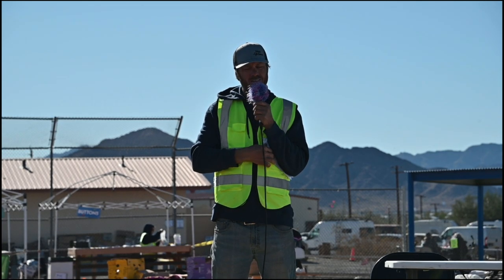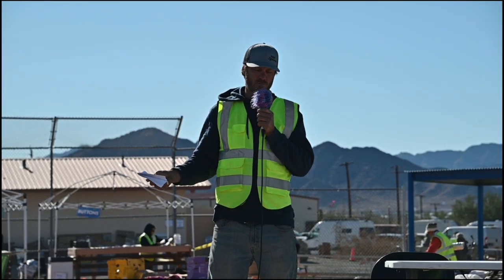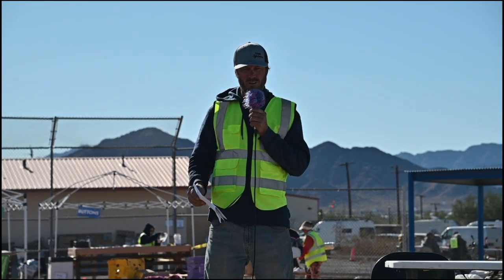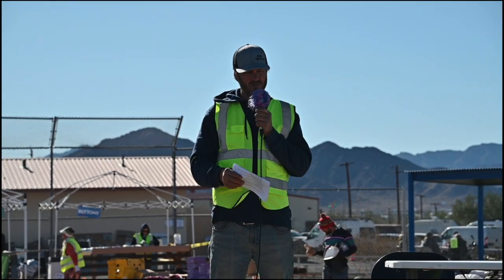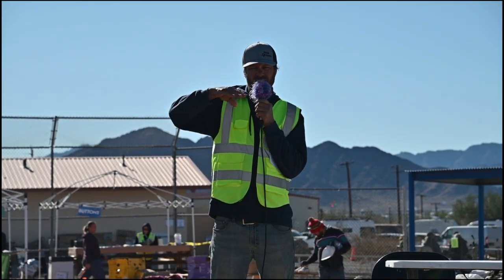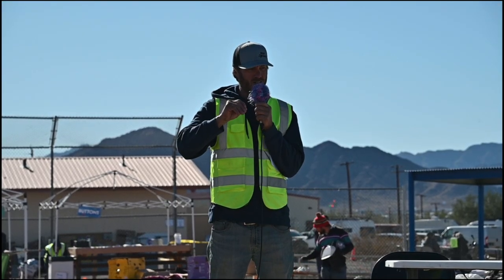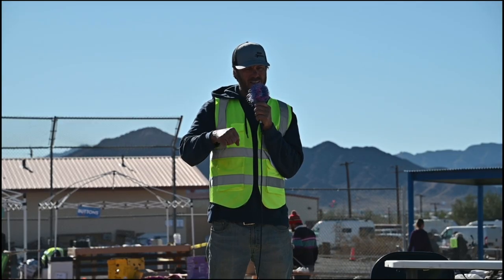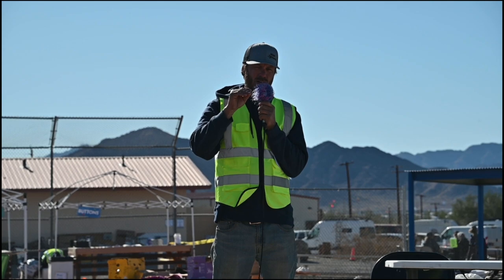So a loose connection on a fuse, if you're trying to pull low power, if you're trying to pull 5 amps, 10 amps, it'll probably go through no worries. But if you've got a 150 amp fuse and you're trying to pull 150 amps through it, and it's going like this, that 150 amps is going to create an immense amount of heat, and it's going to cause a fire.